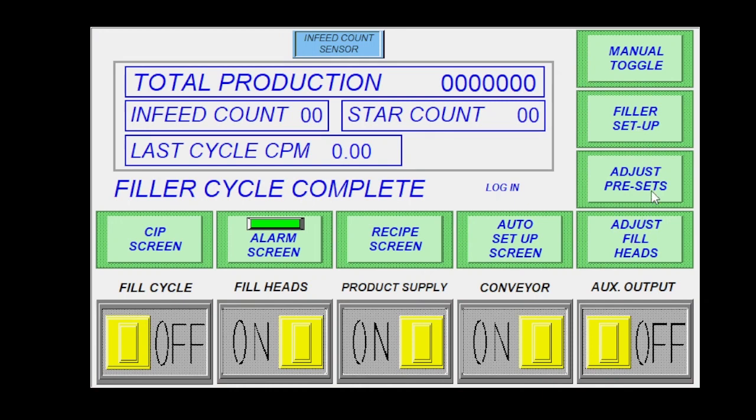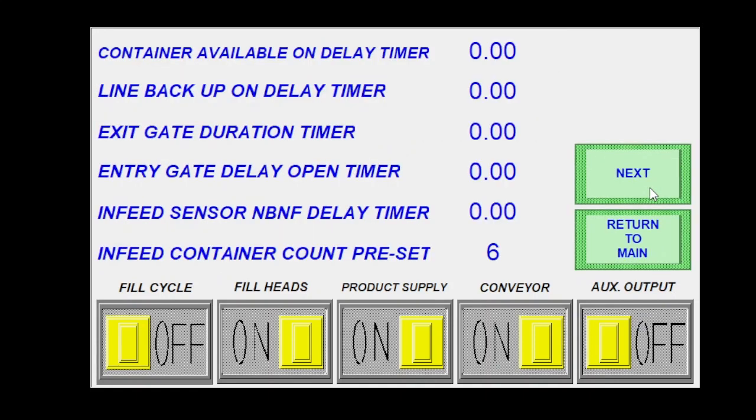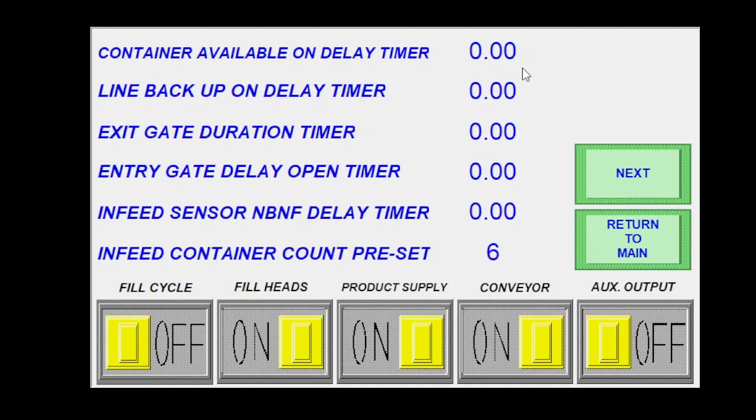The next screen that I would see would be my preset screen. Click on this one. This is going to be where I can adjust all of my timers. This would be if I have a container available setup, which would be just basically saying that I have containers that are ready to come into the machine. This would be the delay of how long a bottle had to sit in front of that sensor before the PLC registered it.